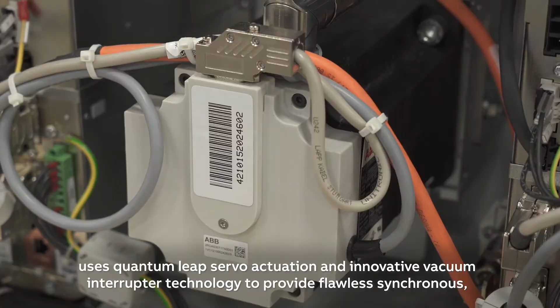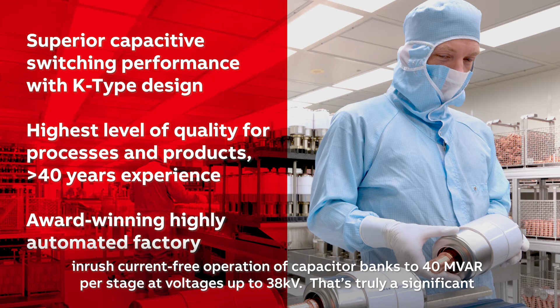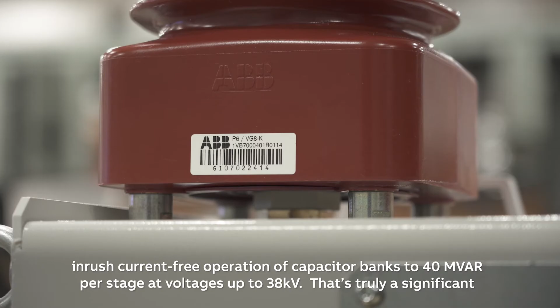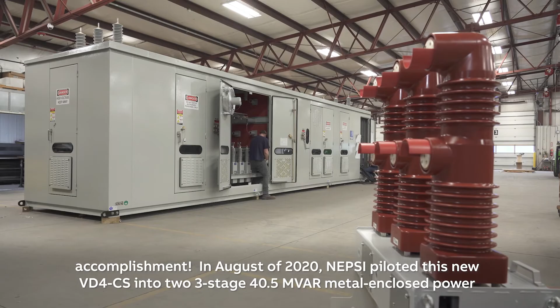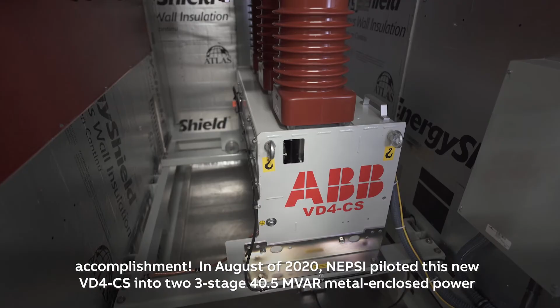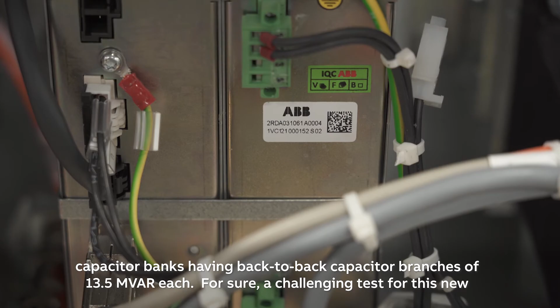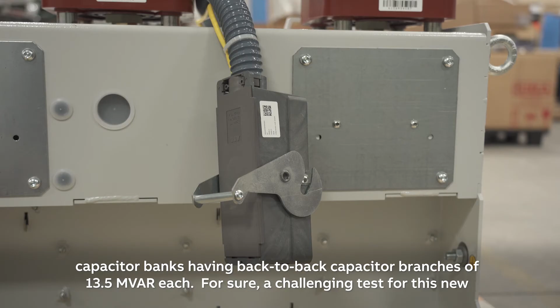That's amazing. The new VD4CS breaker uses quantum leap servo actuation and innovative vacuum interrupter technology to provide flawless, synchronous, inrush current-free operation of capacitor banks to 40 megavars per stage at voltages up to 38 kV. That's truly a significant accomplishment. In August of 2020, NEPSI piloted this new VD4CS into two 3-stage 40.5 megavar metal enclosed power capacitor banks, having back-to-back capacitor branches of 13.5 megavars each. For sure, a challenging test for this new breaker.